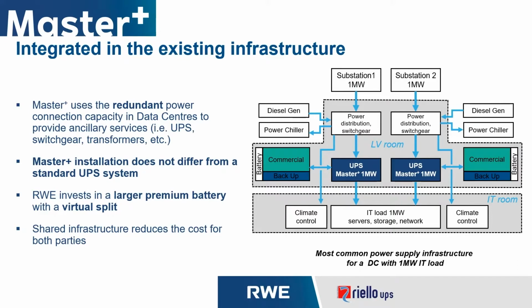Now as you can see from the image on the right there, that is a typical dual stream data center where we have two 1 megawatt UPS systems with the virtually split battery system and the relevant controls. So as you can see, the system does not differ much from a standard UPS and therefore can be integrated into most existing infrastructures.